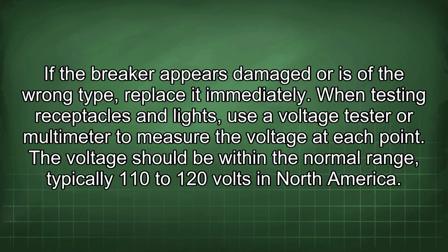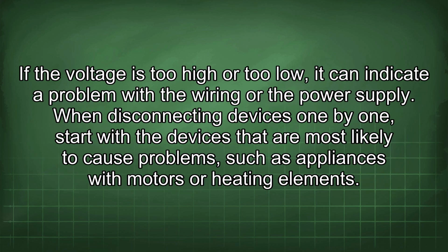When testing receptacles and lights, use a voltage tester or multimeter to measure the voltage at each point. The voltage should be within the normal range, typically 110 to 120 volts in North America. If the voltage is too high or too low, it can indicate a problem with the wiring or the power supply.